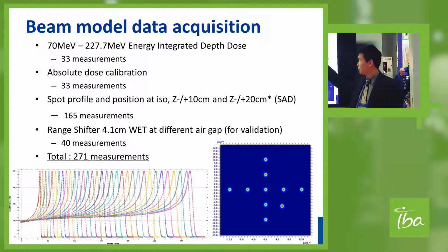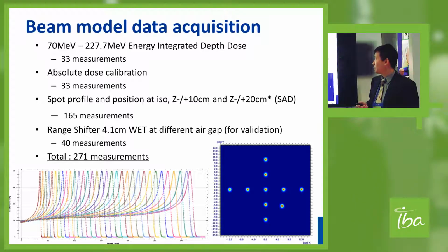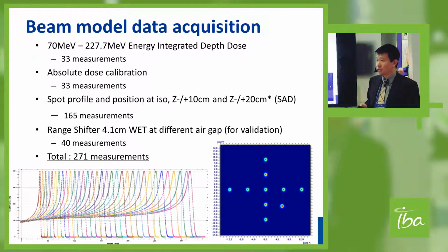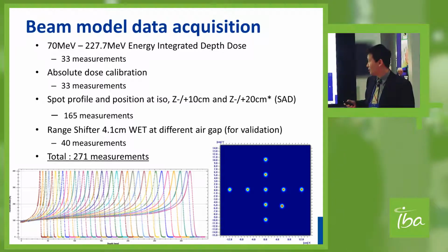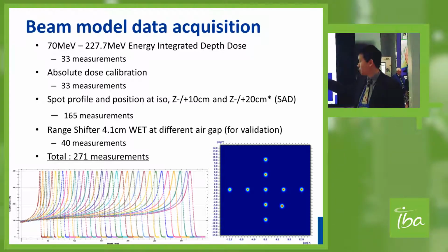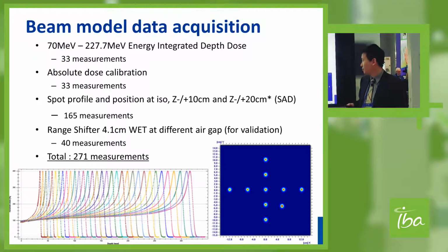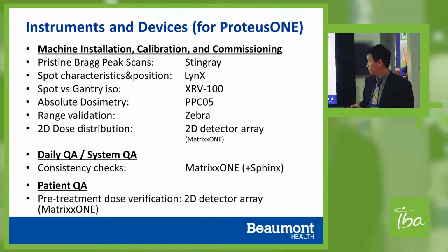The first one is energy integrated depth dose using the Stingray. The second is absolute dose calibration with the different energies, and the spot profile positioning using Lynx with upstream and downstream to calculate SAD. And the last step is the range shifter model, which is not required for RayStation modeling, but you have to collect that for the beam data validation.